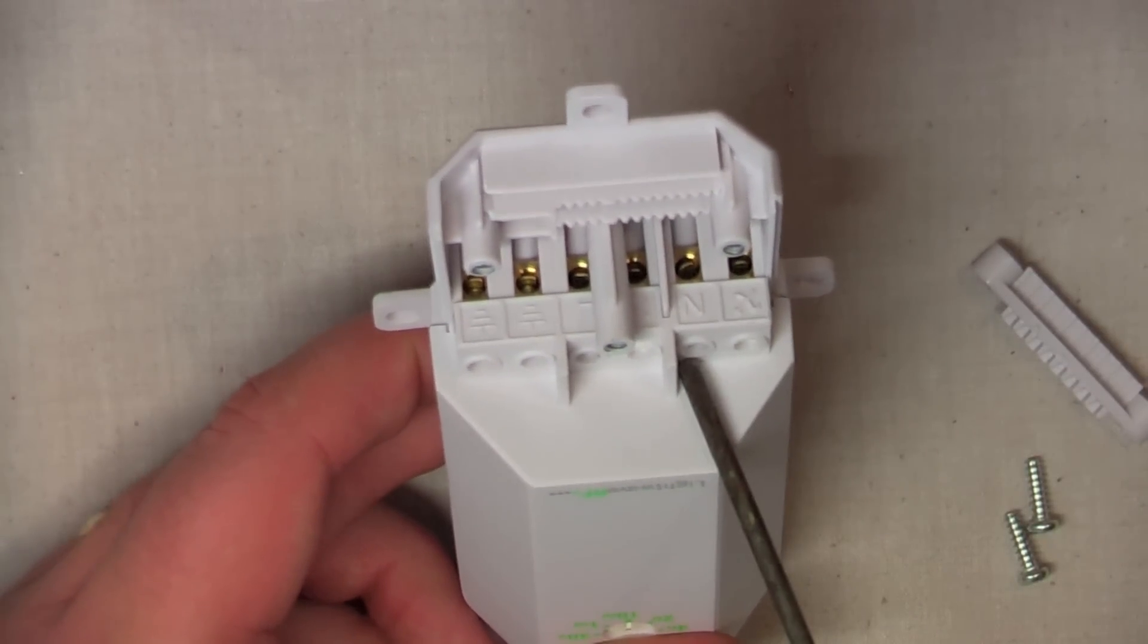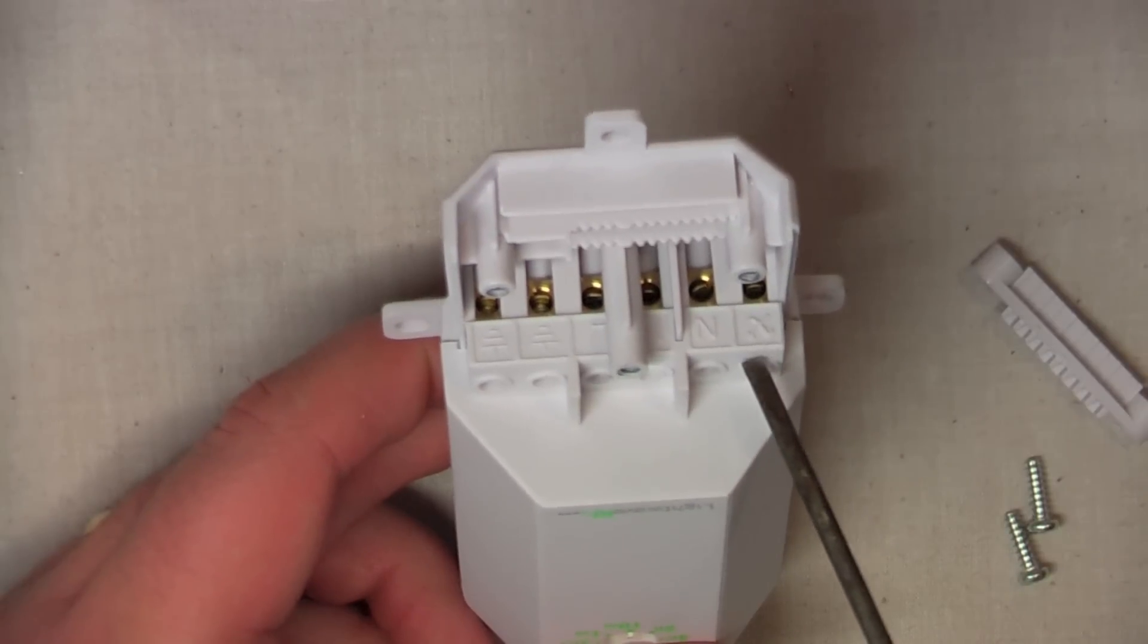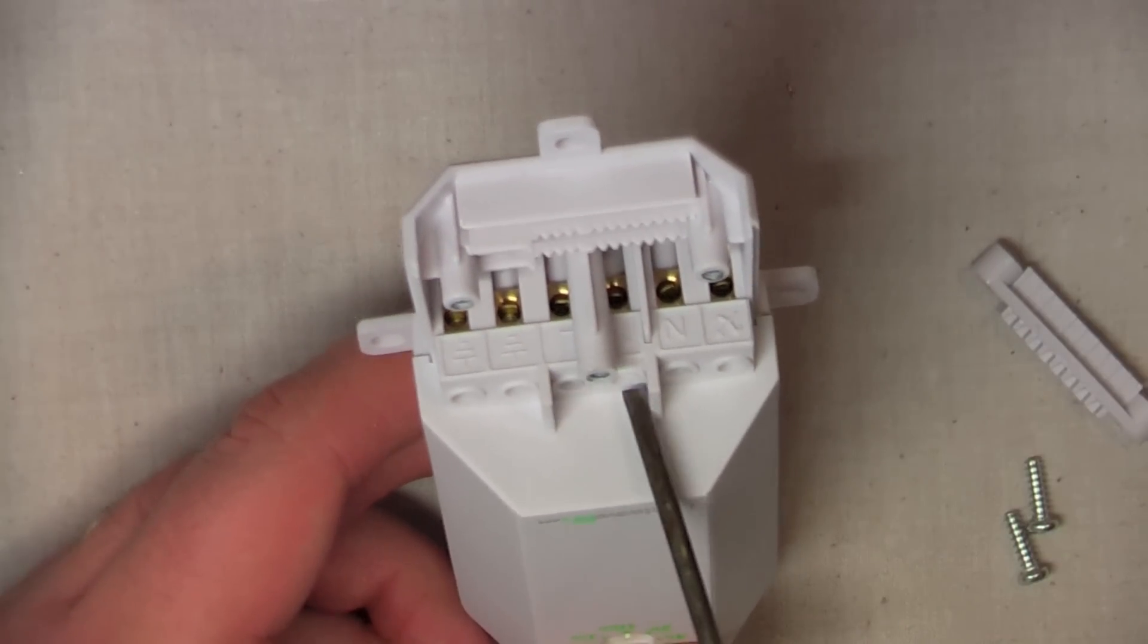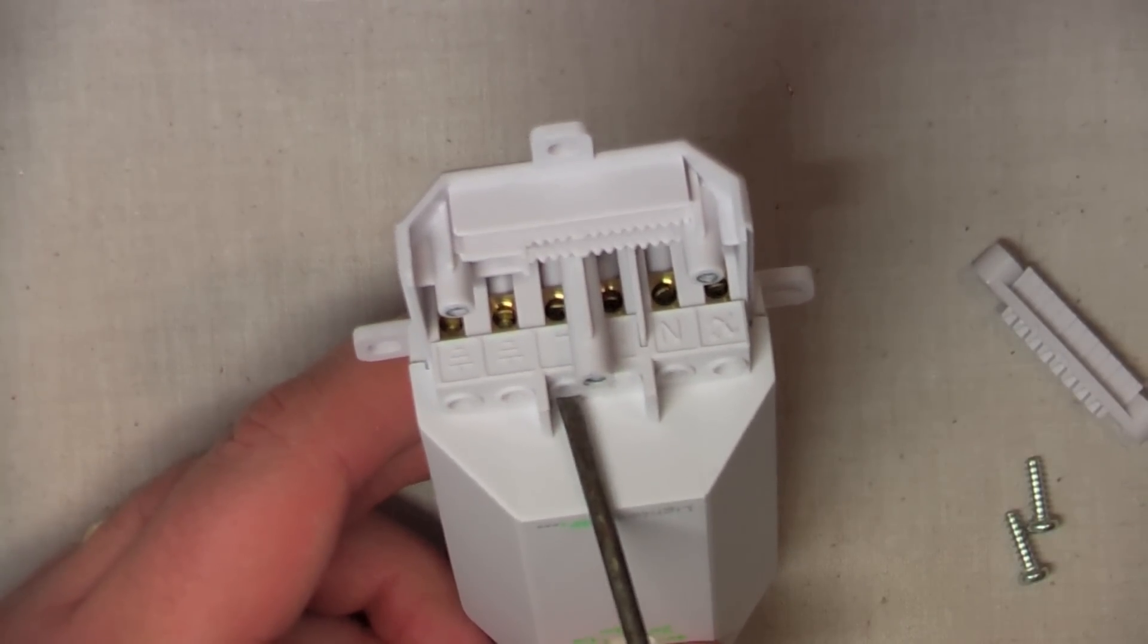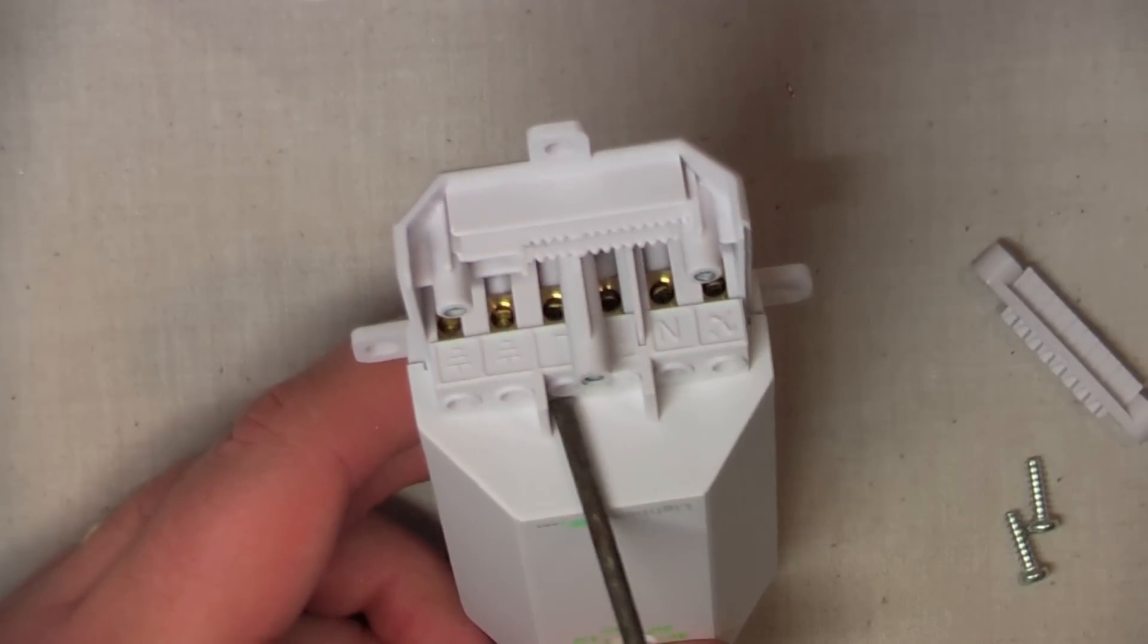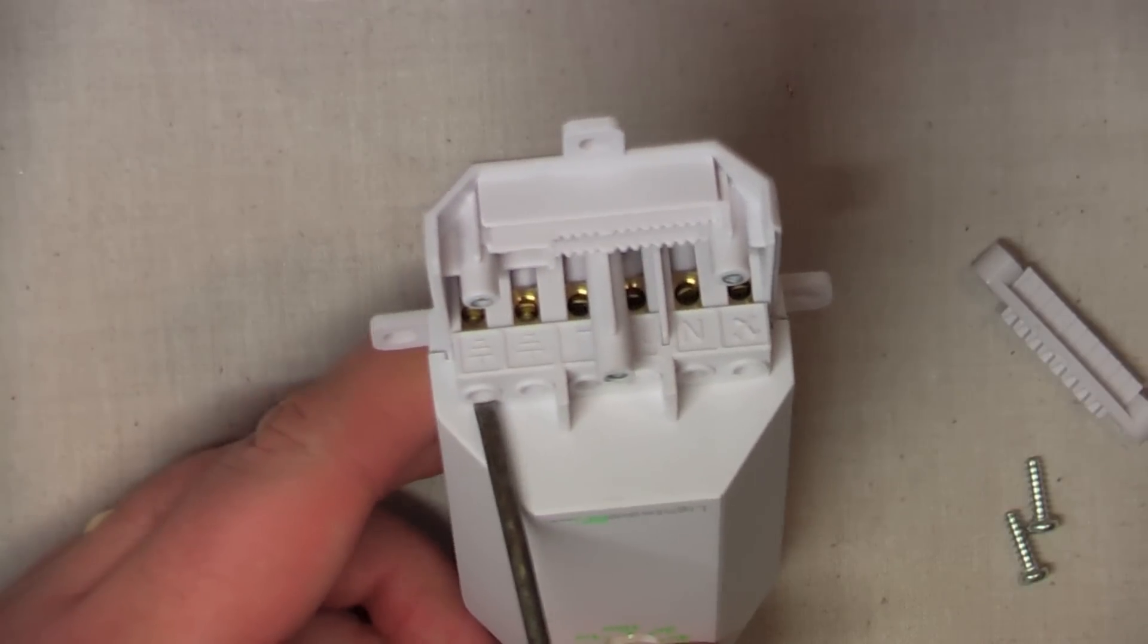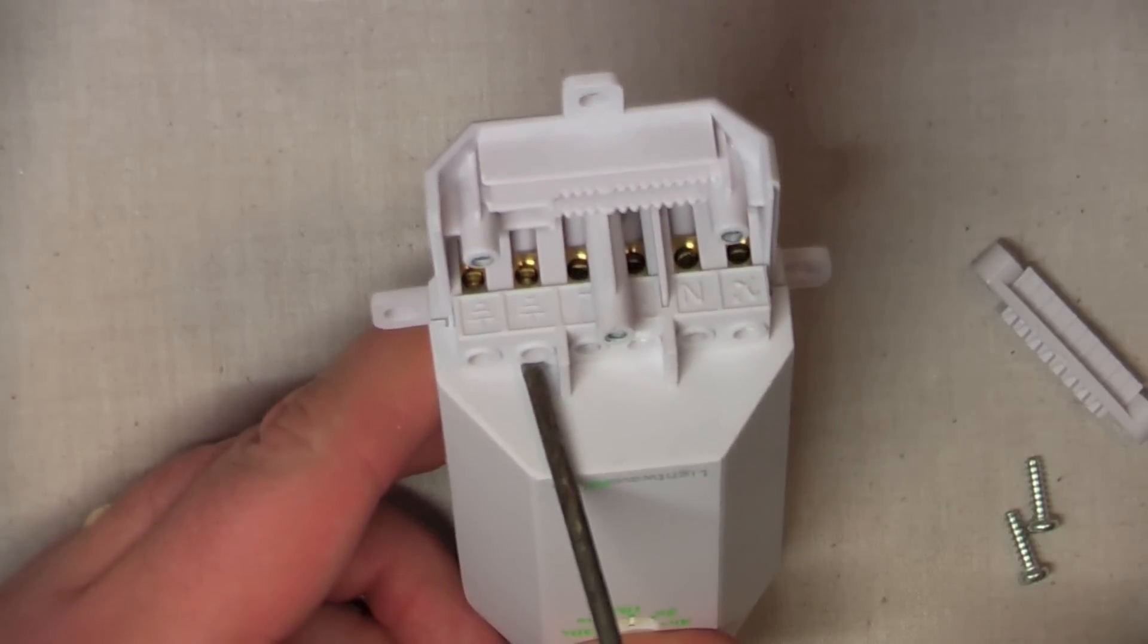These two here are the load side of the relay, so that's basically a switch live and a neutral. The middle two are the supply side, so we need to put some power into here for the device to work and for it to output any power. There's the live there and neutral. And on this end we've got two earth terminals, which you would wire into your earth cables.